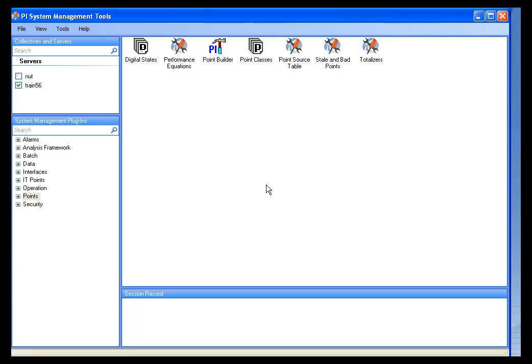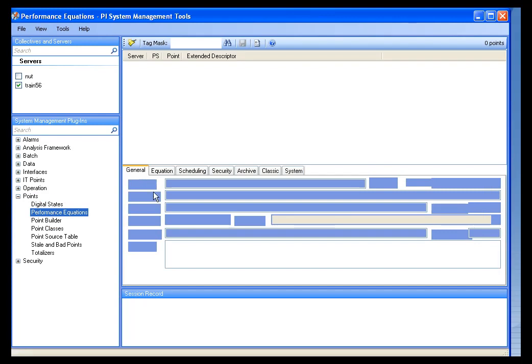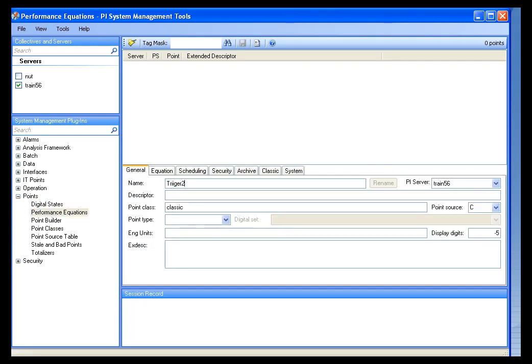I'd like to look at the previous example but throw a little more complexity into it, because I think that'll reflect more real-life situations. Let's say I want to compare my CDT158 tag to my ambient temperature of 80 degrees, but I want to make sure that temperature has been exceeded for more than two minutes — because I don't want little spikes in the ambient temperature to start a new batch. So I want to make sure that value is greater than 80 for more than two minutes before I start my batch. I'm going to create a performance equation tag and call this trigger2.